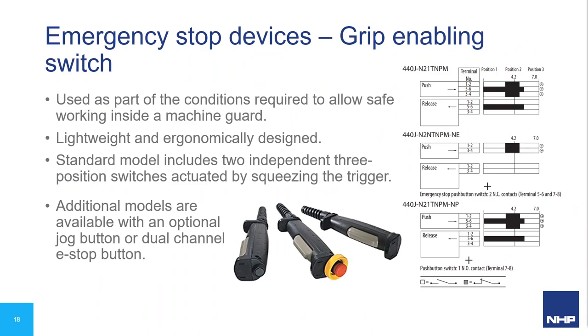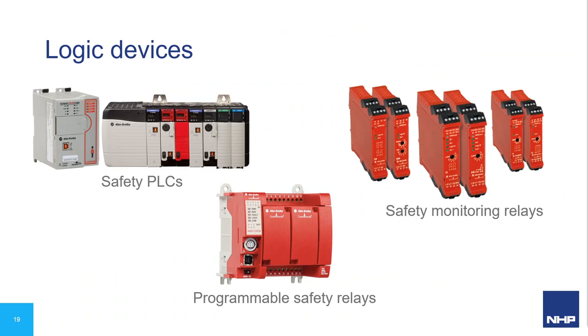Finally for input devices, the grip switch is used as part of the conditions to allow safe working inside a machine guard — typically when you need to enter a guarded area while the machine operates at safe speed or when quick access to turn the machine off is needed. Squeezing the trigger enables the machine; releasing it turns it off. Some models offer an optional jog button or a dual-channel e-stop button. That covers the safety input devices — now we move to the logic devices, ranging from simple single-function safety relays to fully-fledged PLCs with both standard and safety functionality.